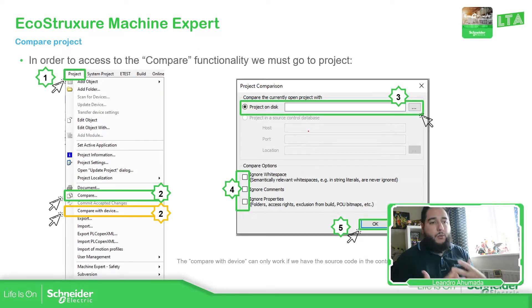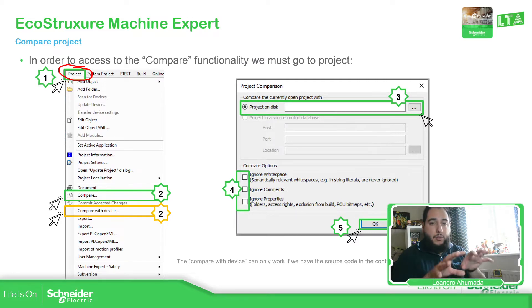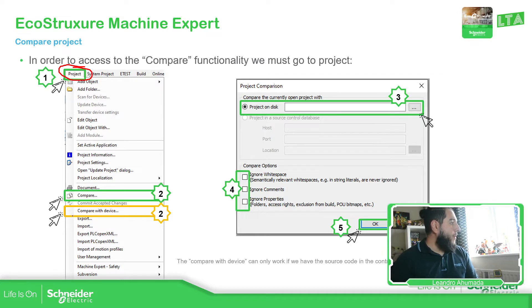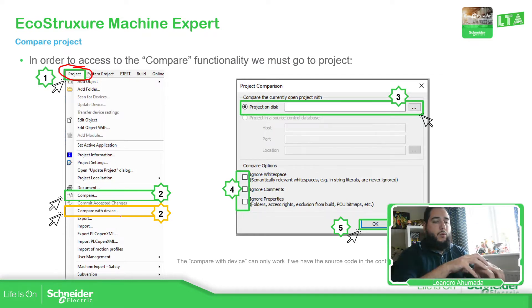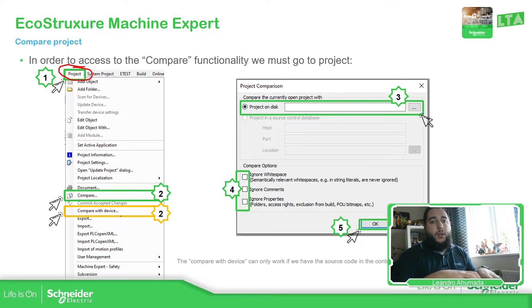So how to make the comparison in our project — it's very simple. We just need to go to Project and then select Compare, if we have the two projects on the same laptop, or we select Compare with Device when you have the project on your laptop and want to retrieve the source code from the controller in order to make the comparison.